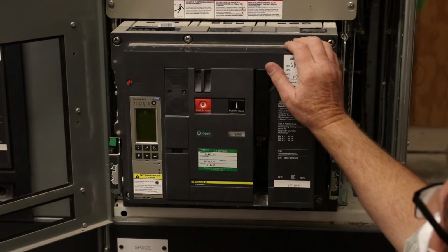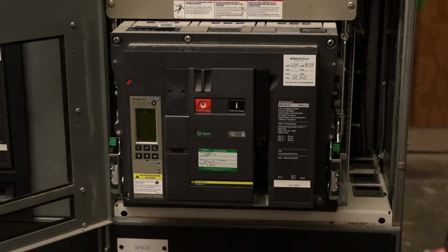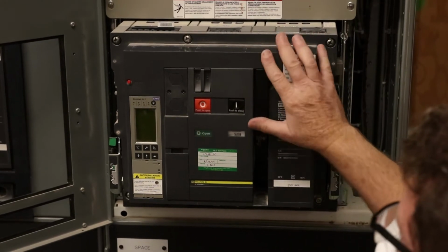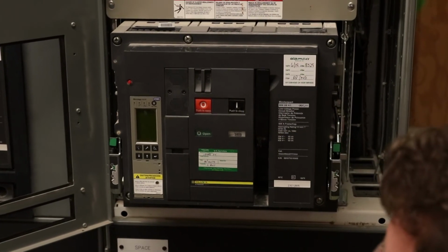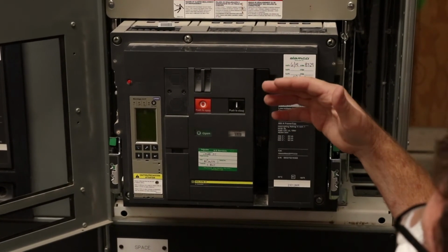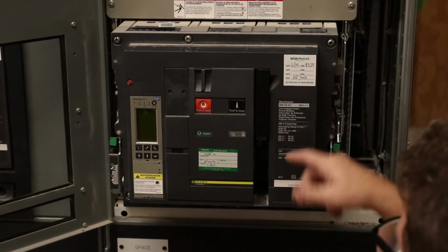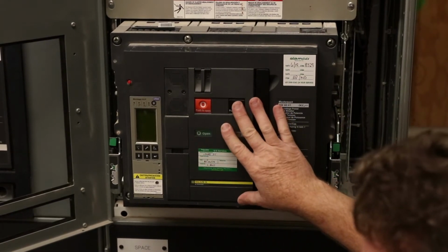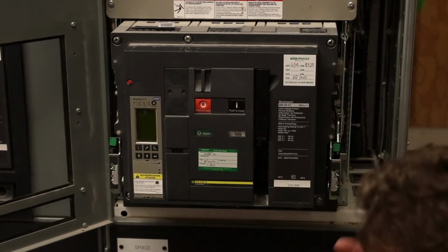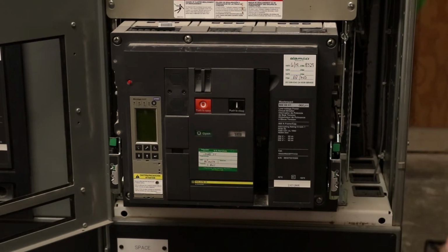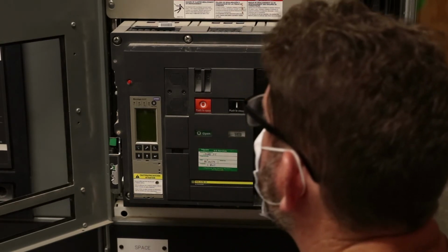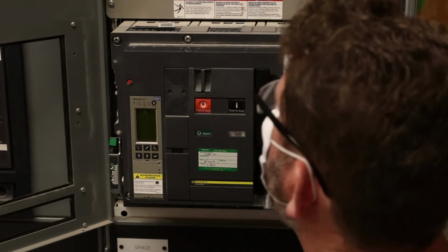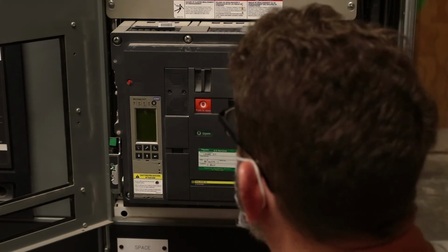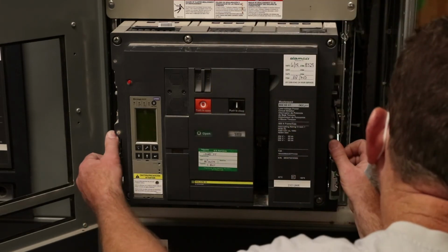Any draw-out breaker, as you pull it out of the cell to work on it, it's required by NEMA standards that the breaker will come out open with any springs discharged. That's just a safety measure to make sure that someone doesn't pull the breaker out, stick their hands in and get them caught in the springs.